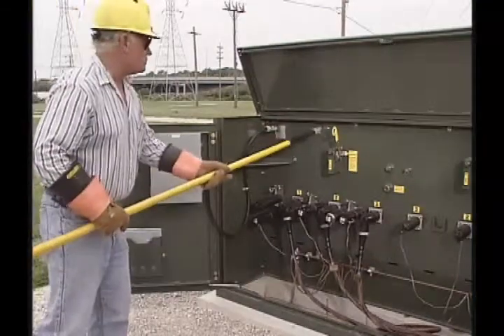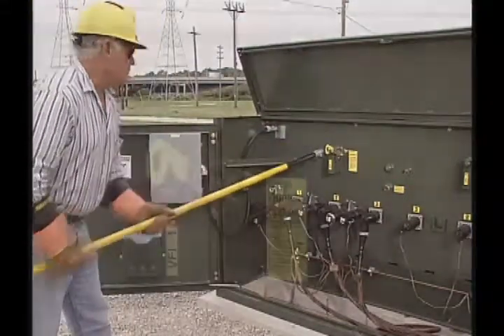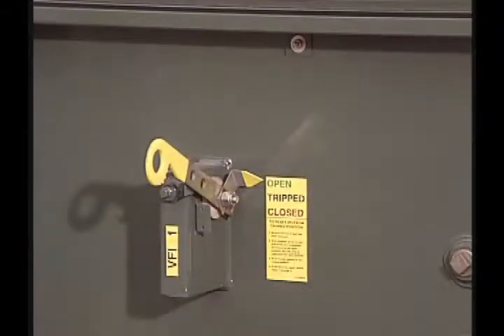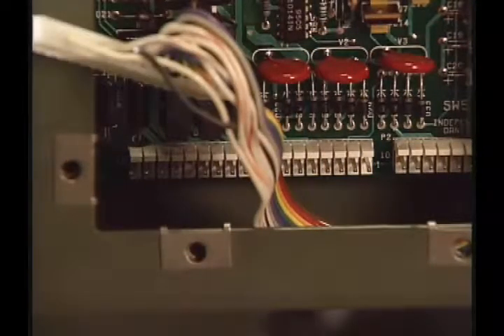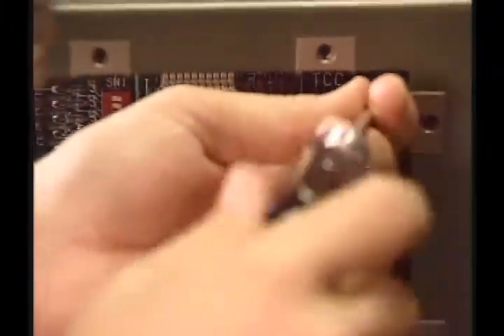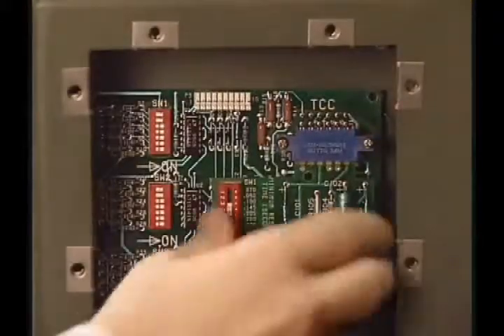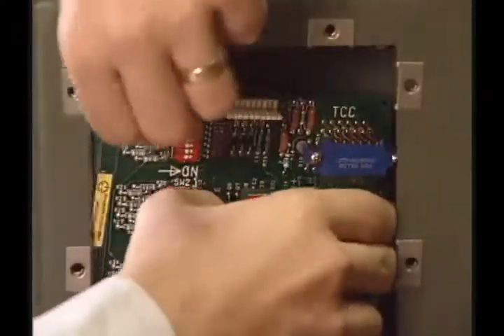De-energize the switchgear according to locally approved procedures before removing the circuit board. Then move the VFI's operating handles to the open position. Disconnect the VFI control cable from the pin connector labeled P1 on the circuit board. Next, remove the 4 circuit board mounting screws. Now, carefully remove the circuit board.